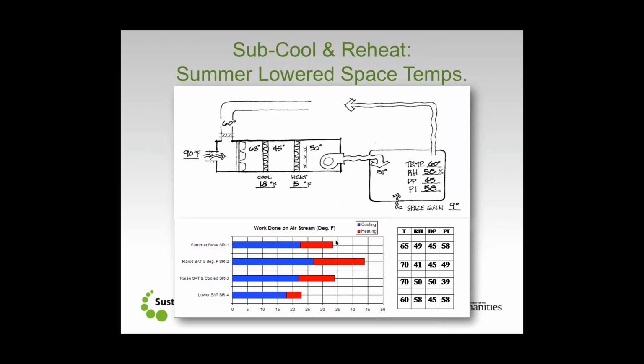So if we look at it and say, all right, I've got a library and archive collection, and there aren't a lot of metal components in here. I'm comfortable at 58% relative humidity. It's not great, but it's pretty good. And notice, I've run the numbers on the dew point calculator, and if I do 60 degrees and 58% RH, I wind up with the same preservation index, or the same rate of chemical decay, that I did earlier at 65 degrees and 49% RH. All right, so moot point.